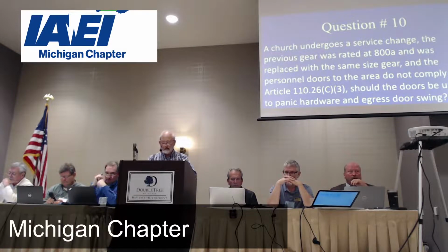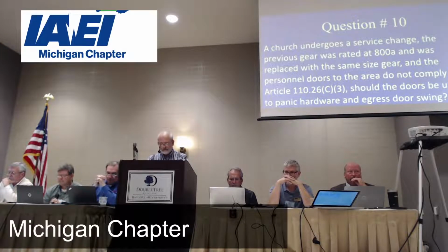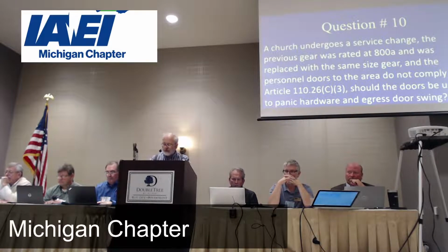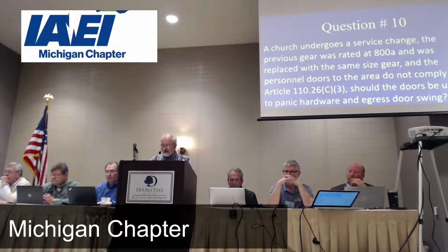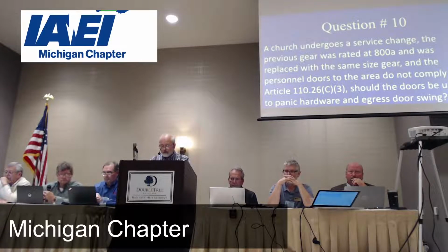Question number 10. Tim, a church undergoes a service change. The previous gear was rated at 800 amps and was replaced with the same size gear. And the personnel doors to the area do not comply with Article 110.26(C)(3). Should the doors be updated to panic hardware and egress door swing?